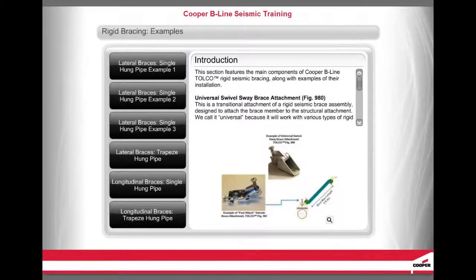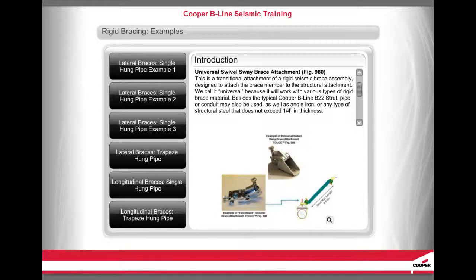This section features the main components of Cooper B-Line Tolco rigid seismic bracing. The Universal Swivel Sway Brace Attachment, Figure 980, is a transitional attachment of a rigid seismic brace assembly designed to attach the brace member to the structural attachment. It is called universal because it works with various types of rigid brace material — besides the typical Cooper B-Line B22 strut, pipe, conduit, angle iron, or structural steel not exceeding one-quarter inch thickness may also be used.